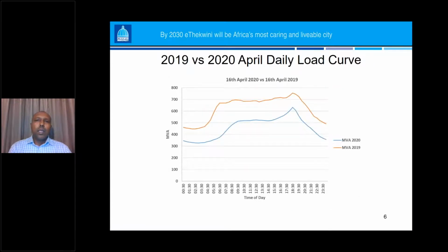In this graph, what I'm trying to show is the consumption pattern or daily load curve for our largest substation, which is a 275 kV to 132 kV substation. We roughly bring in load or power from Eskom at this substation, and it feeds possibly 60 to 65% of our customers. If we look at the daily load curves for 2019 versus 2020, I've taken the day with the maximum demand and compared them.